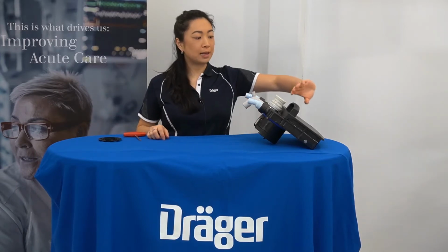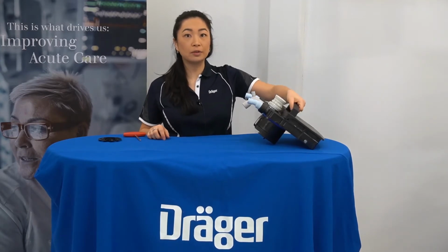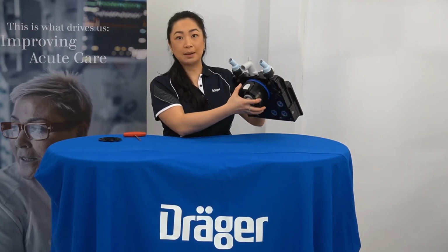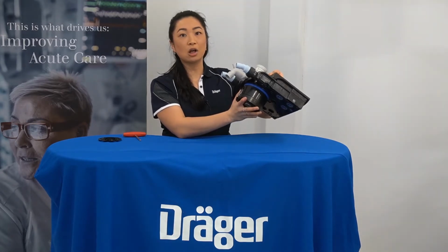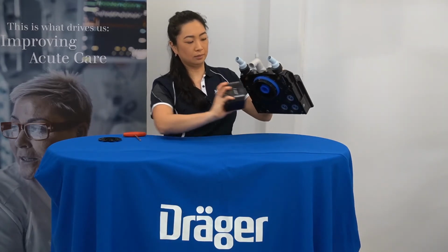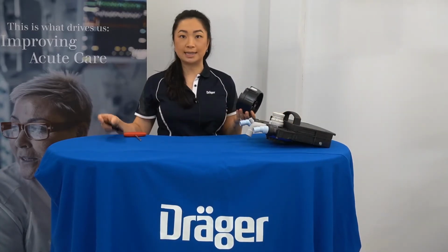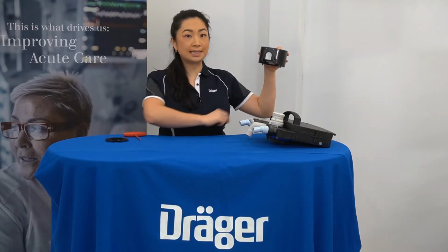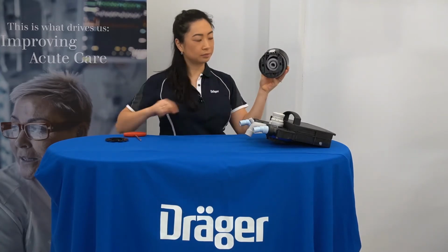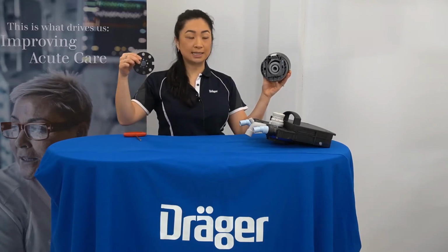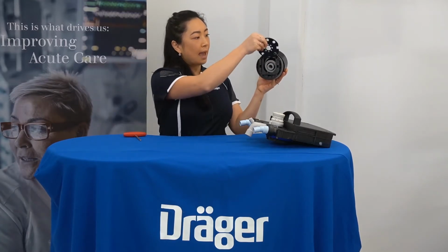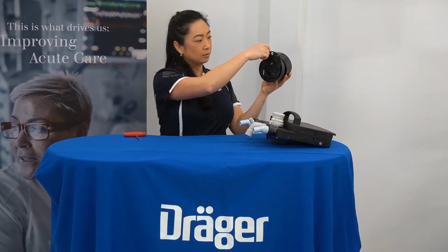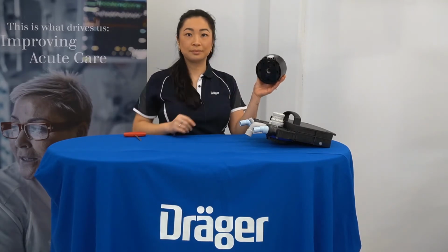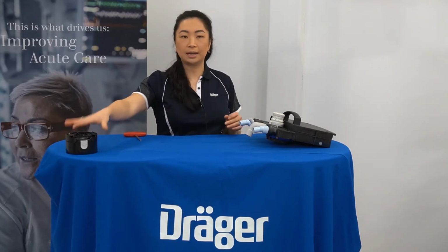To start, we'll be removing the click adapter first. So, placing one firm grip on the handle of the breathing system and one on the click adapter, turn counterclockwise to remove. At this point, it is good practice to insert the cleaning disc. So, to open up the click adapter, press the grey button. Align the straight sides of the disc to the straight sides seen here and slide the disc in. Click shut, and this can be placed to the side.